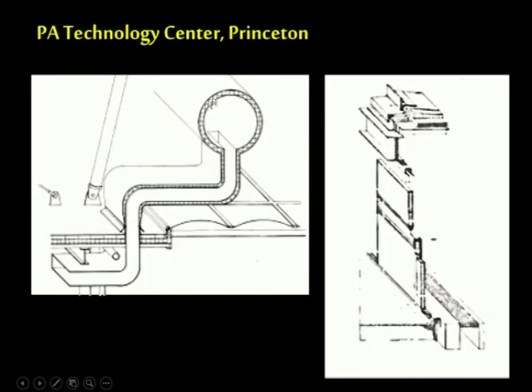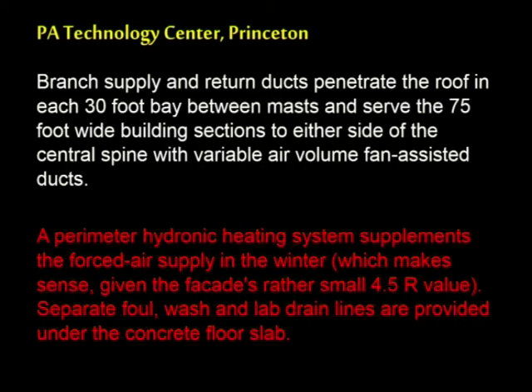Here is the detail of the AC system, where above this deck is the interior of the building and this is the exterior of the building. On the exterior of the building, the air duct is insulated. On the bottom portion it is not insulated, but on the top portion it is insulated. Branch supply and return ducts penetrate the roof in each 30-foot bay between masts and serve the 75-foot wide building sections to either side of the central spine with variable air volume fan assisted ducts.